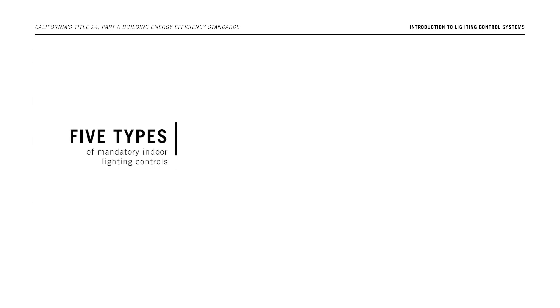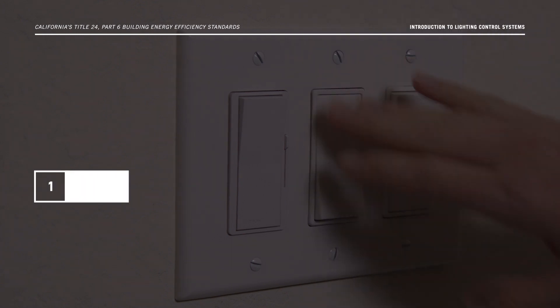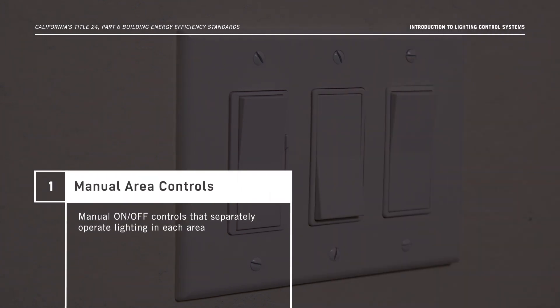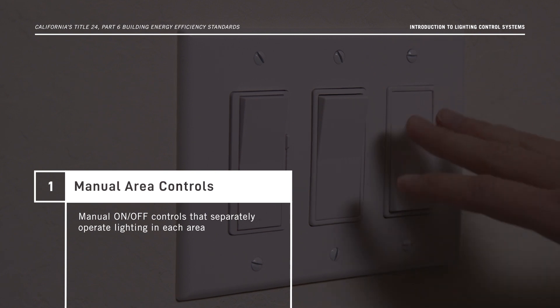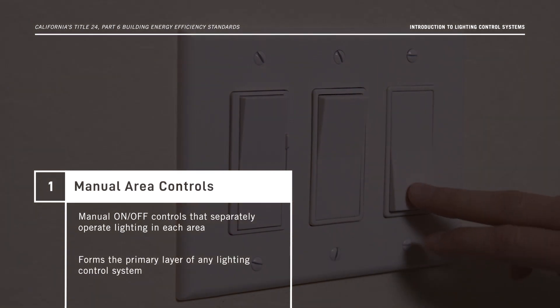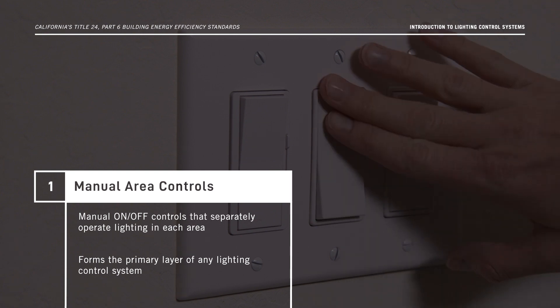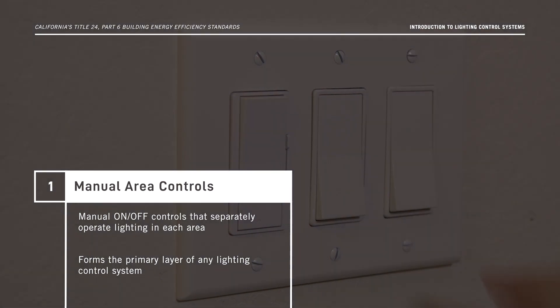Now we'll tell you about the five types of mandatory indoor lighting controls, and we'll review the control interactions required under the Energy Code. Starting with manual area controls — they're manual on-off controls that separately operate lighting in each area. An area is any space with ceiling height partitions or walls. These controls form the primary layer of any lighting control system and have been required under the Energy Code since its inception in 1978.